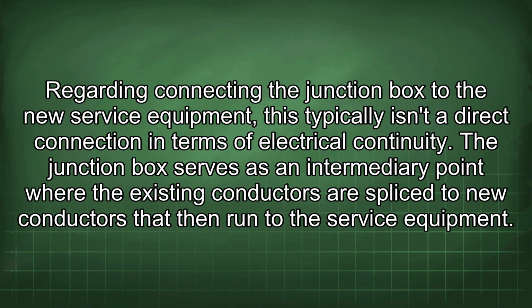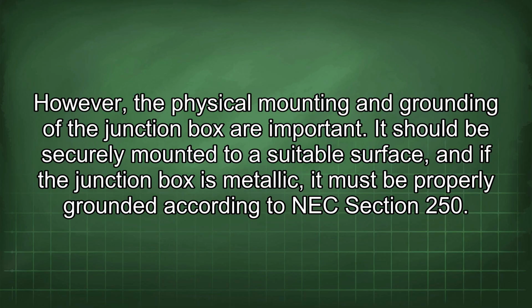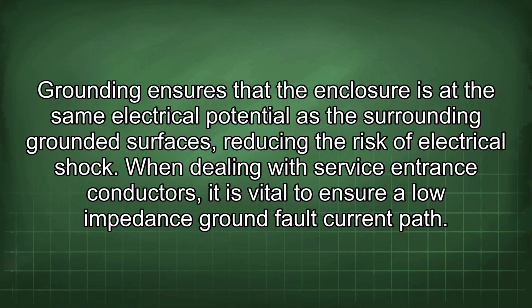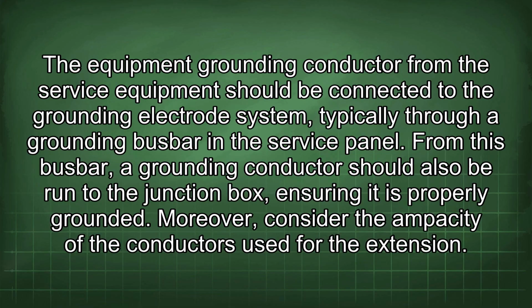Regarding connecting the junction box to the new service equipment, this typically isn't a direct connection in terms of electrical continuity. The junction box serves as an intermediary point where the existing conductors are spliced to new conductors that then run to the service equipment. However, the physical mounting and grounding of the junction box are important. It should be securely mounted to a suitable surface, and if the junction box is metallic, it must be properly grounded according to NEC section 250. Grounding ensures that the enclosure is at the same electrical potential as the surrounding grounded surfaces, reducing the risk of electrical shock. When dealing with service entrance conductors, it is vital to ensure a low impedance ground fault current path. The equipment grounding conductor from the service equipment should be connected to the grounding electrode system, typically through a grounding busbar in the service panel. From this busbar, a grounding conductor should also be run to the junction box, ensuring it is properly grounded.